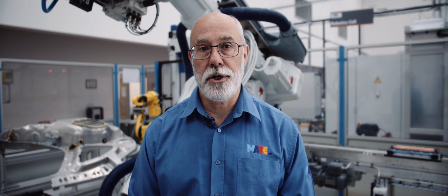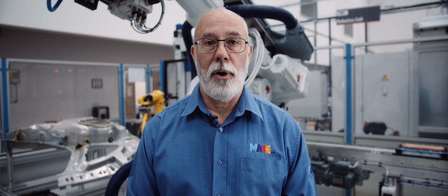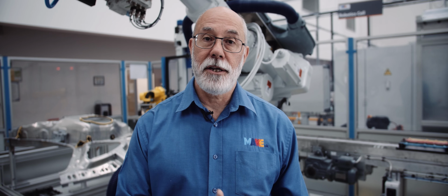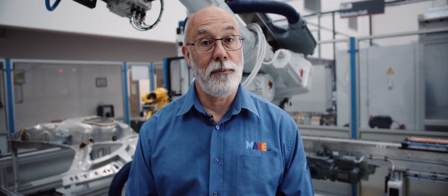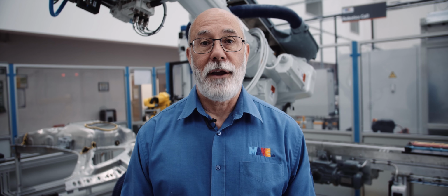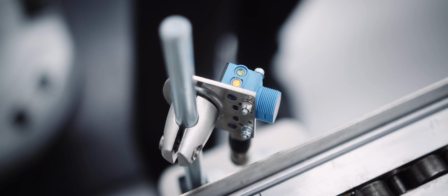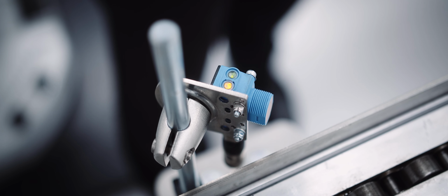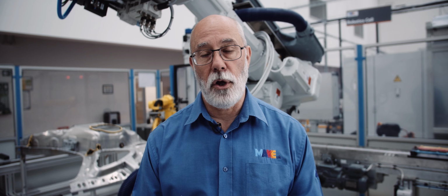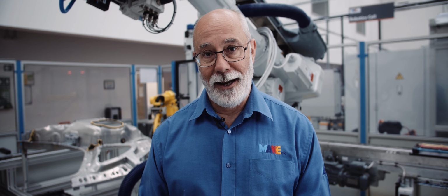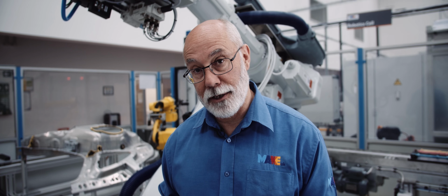Okay, so what we're going to have a look at here is a practical example of the 5 whys in action. We're back to the problem where the robot cell has stopped working, it's not working as it should, and by analysing the data on the HMIs and other bits and pieces that we've got access to, we can find out that it's one of the electrical sensors, the photoelectric sensors, which isn't getting a signal. So we've shut the cell down, opened it, locked it all out so it is safe to come in here and work, and we've found out that it is this photoelectric cell down here which is causing the problem.